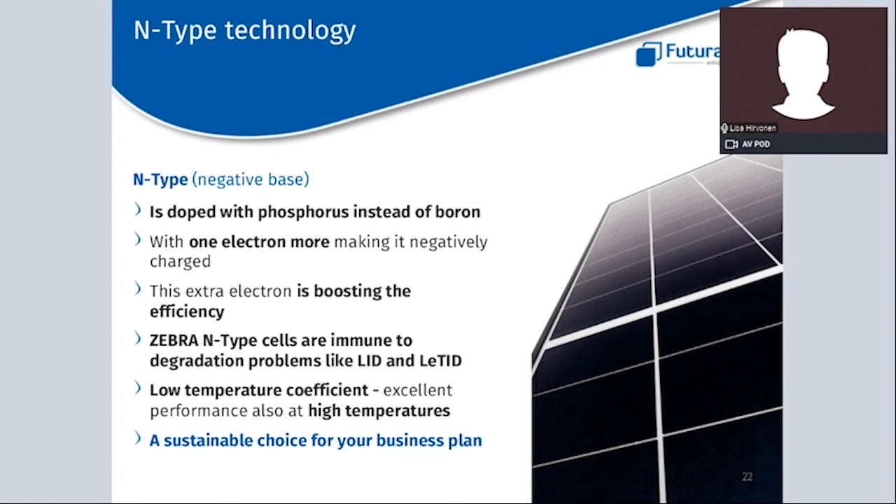The Zebra N-type solar cell is also immune to degradation problems such as LID and LeTID. N-type cells, and in particular the Zebra cell, are characterized by a lower temperature coefficient compared to P-type cells, thanks to a higher cell voltage. Modules with N-type cells are priced at a higher level compared to P-type modules, but when considering a long-term investment — expecting a system to operate for at least 25 years — N-type modules are often shown to be a sustainable choice. The extra investment will pay back itself with time.